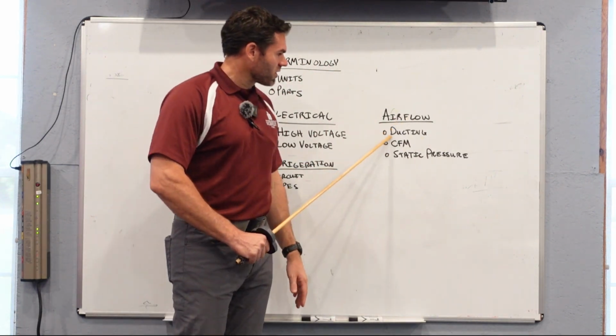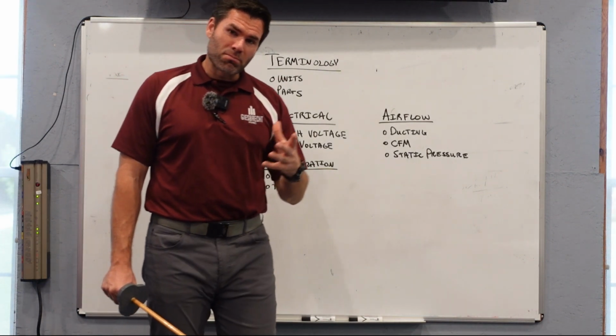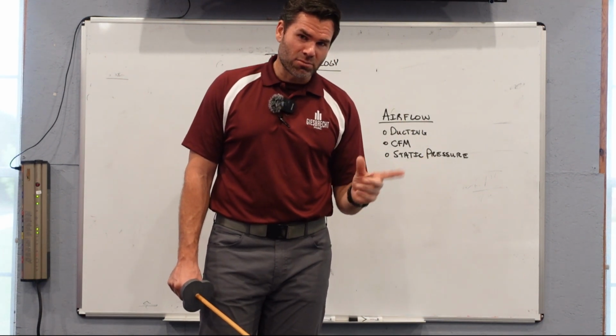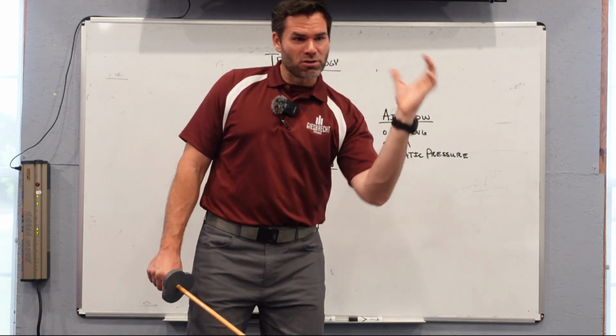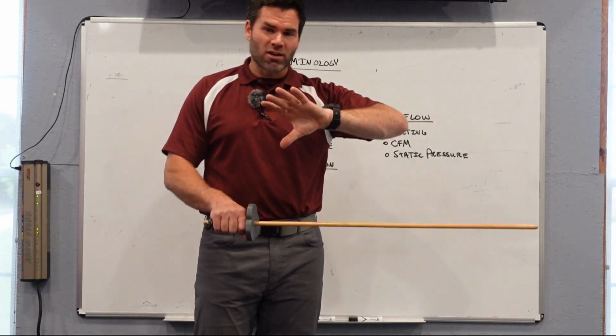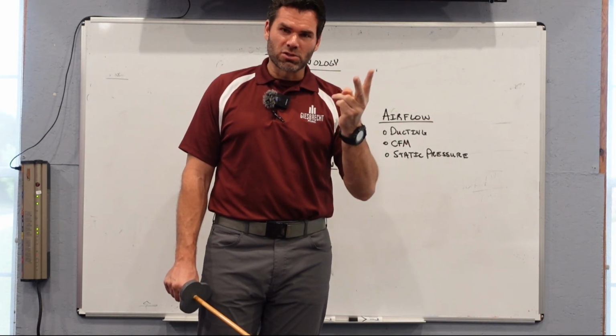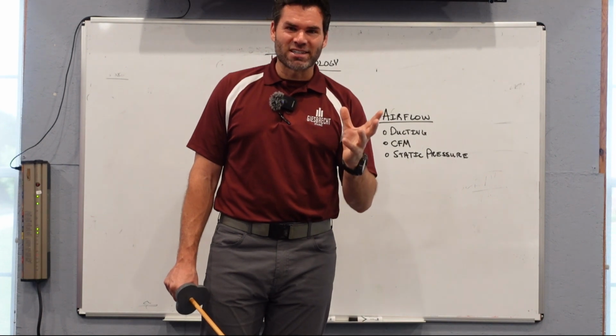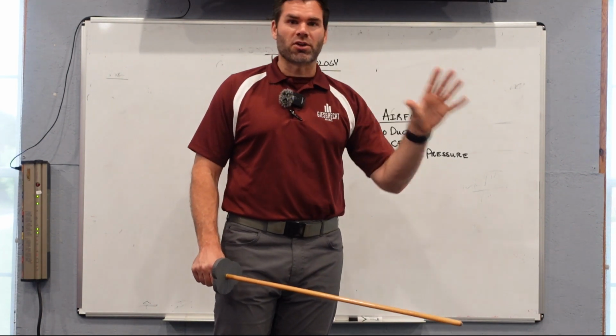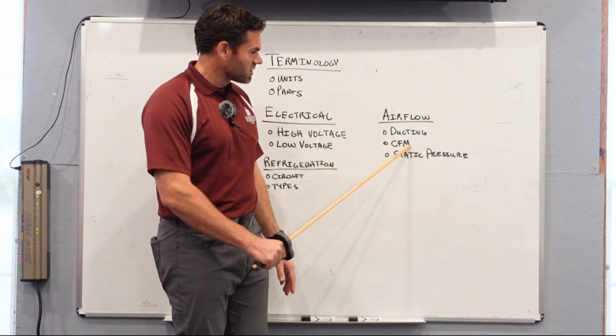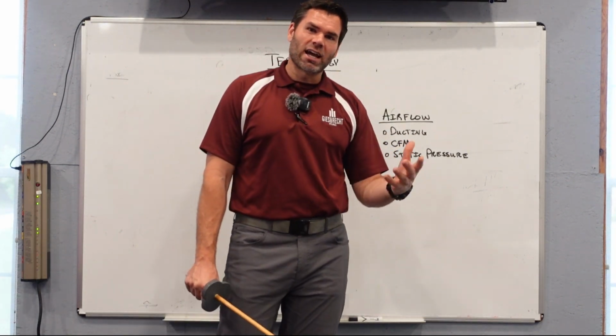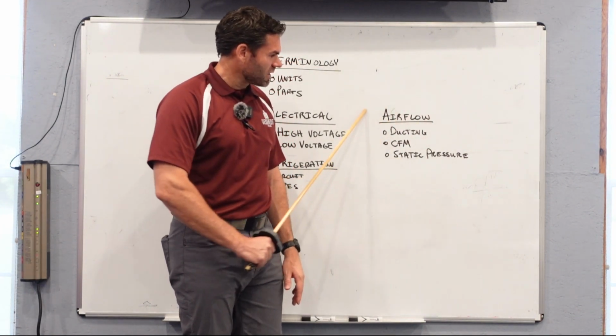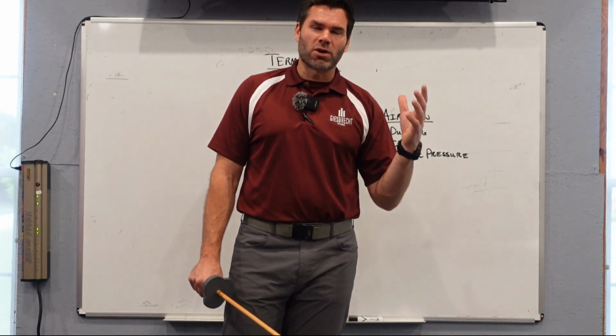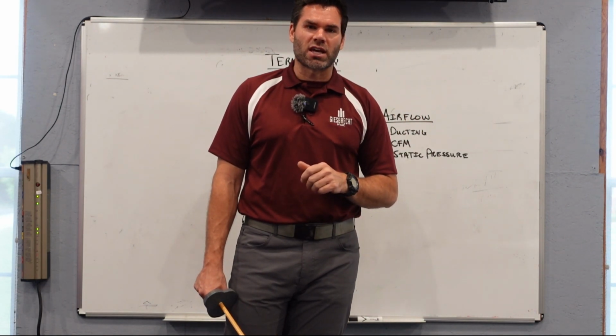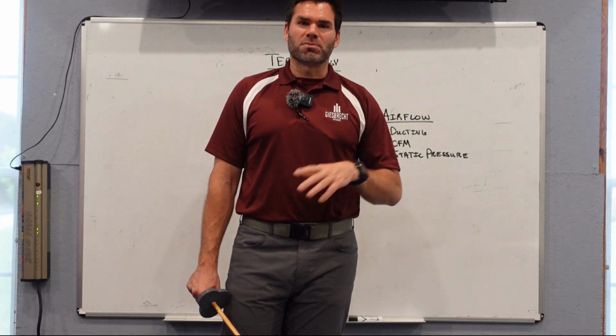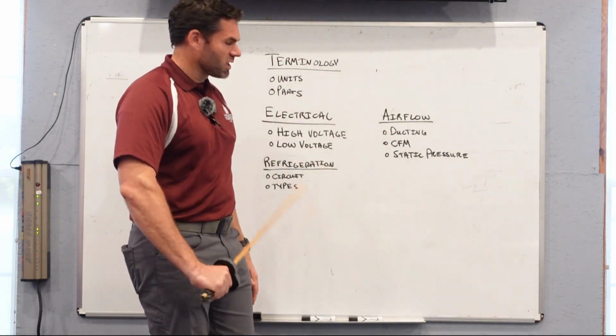You need a good understanding of ducting—how do you design it? Do you design it with a sharp 90-degree turn, or try to make it a straight run? You also need to understand the size of duct required to move the correct amount of CFM, so you need a good grasp of cubic feet of air per minute. And finally, static pressure—understanding what static pressure a system needs to function efficiently. These are fundamental things you need to understand.